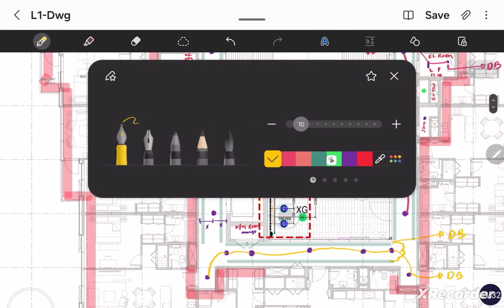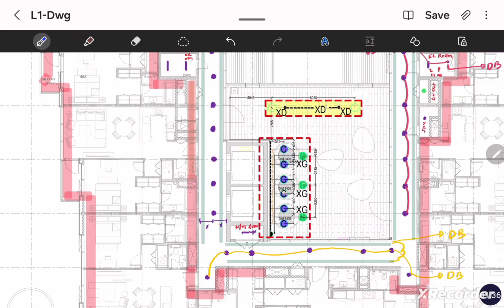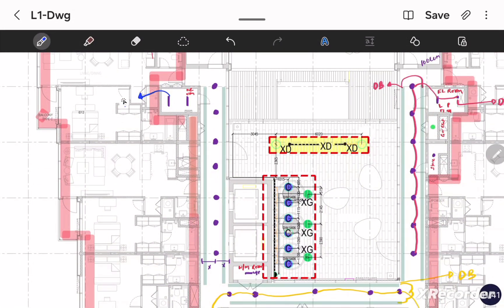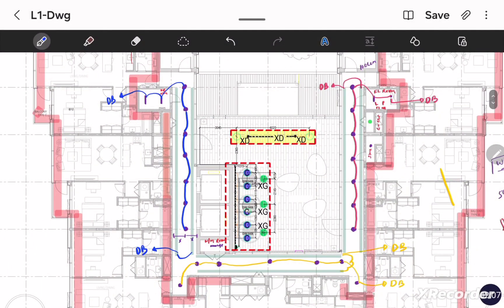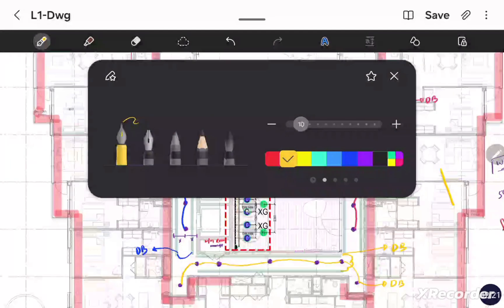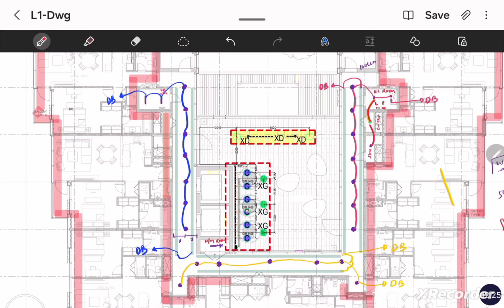We make another loop between the two hidden lights and give it to the DB. So we have two circuits in each corridor: two Red circuits for one corridor, two Yellow circuits for the other, and for the third corridor we assign Blue circuits to balance the load. The Blue circuit goes to the DB and loops through all nine lights, then another circuit for the hidden lights. After completing all corridors, we loop the service room lights. We have now completed the first floor common area corridor and service room light circuit formation.